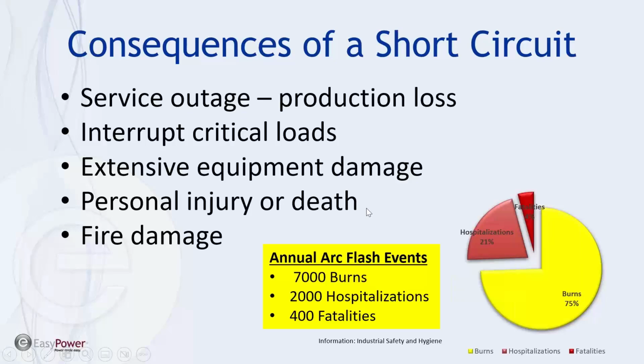Extensive equipment damage. Sometimes, especially if it's main switchgear, you don't just get that main switchgear overnight. It's going to take weeks of design to make sure that it's going to fit, and it may have to be built. So it could be weeks of outage time. Personal injury and death, we're going to show a case in a second on that, and hopefully that doesn't happen. But because of your miscoordination or not having things rated for short circuit, it could cause these major issues if somebody happened to be in those areas. And then fire damage. If there's combustibles in the area when you have this big arc flash event, then things catch on fire, and now you've got this catastrophic fire that takes your facilities down.